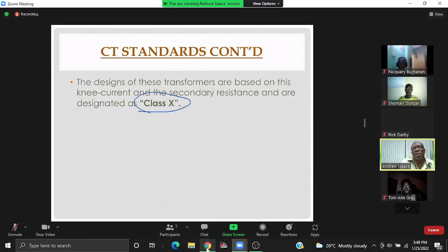So you would have had IP, your primary current, being a function of the voltage and the resistance and inductance of the system. Of course, one of the things we need to bear in mind is that in your power system, especially for your lines, the inductance is much larger than your resistance. And so one standard angular measure that we take is that the angular displacement between the two is in the 78 degrees. And we'll speak to the importance of that at a later time.